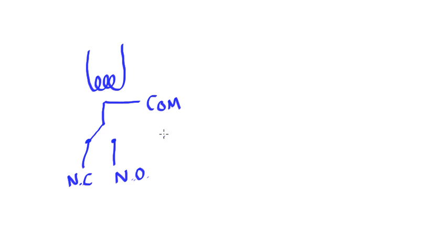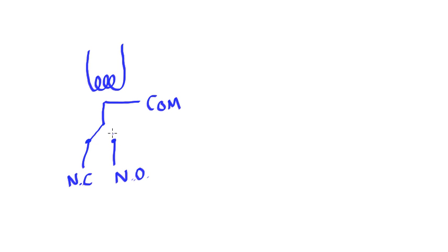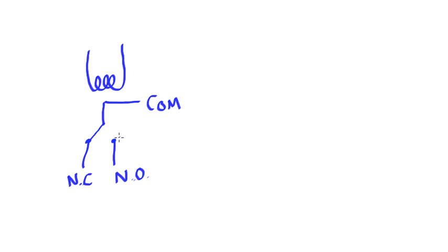What I mean by this is without energizing this coil, the path between the common and this normally closed will be made. When I energize this coil, this pathway will be broken and the pathway to the normally open will then be closed. So energizing the coil completes this part of the circuit. De-energizing the coil completes this part of the circuit. You could use one, the other, or both as a part of your circuit depending upon what you want to have happen.